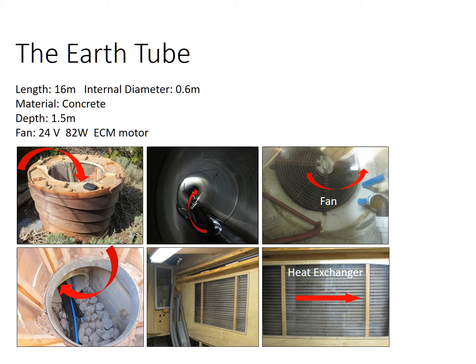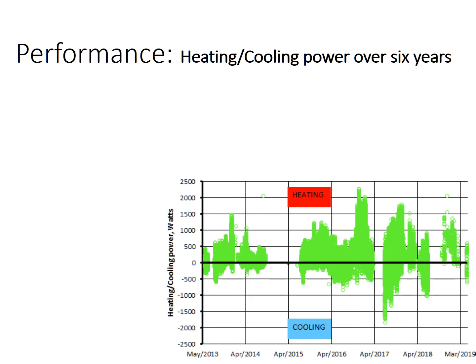The air goes from the fan into this heat exchanger here. The air is passed through these narrow glass tubes, and outgoing air from the building is passed across on the other side. So, to some of the results. This is quarter-hourly data for 6 years, and this has been analysed in some detail. So looking at the cooling power or heating power, what do we find? The x-axis here goes from May 2013 by year up to March 2019, and heating is above this line and cooling below this line. The y-axis is the cooling power in watts, or heating power in watts.